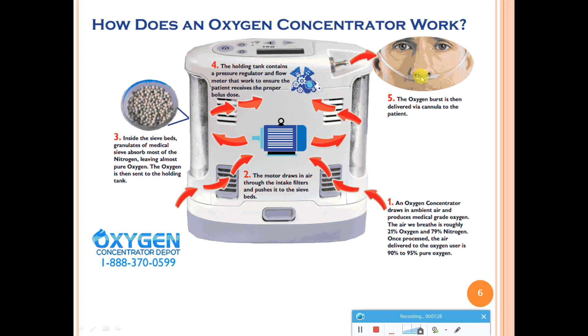Coming to a few advantages of these oxygen concentrators: they are portable, they can be used 24/7, and their lifespan is around 4 to 7 years. Within the systems there are filters inside so that no bacteria, virus, fungus, or anything comes inside. You have to take care of these filters, monitor them every now and then, and these filters can be changed. It can work even on UPS systems, and no refills are required as in the case of oxygen cylinders, which were used prior to oxygen concentrators. With oxygen cylinders, you need to refill them every now and then.